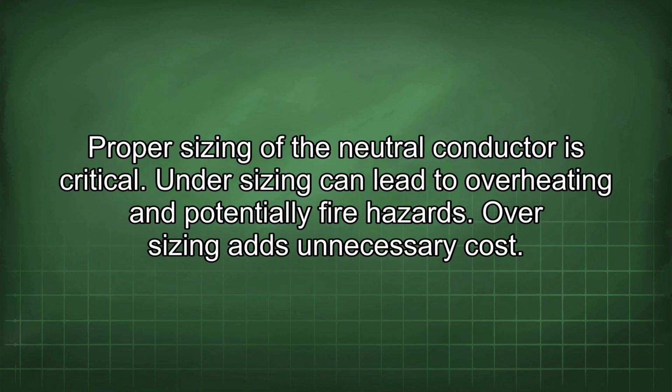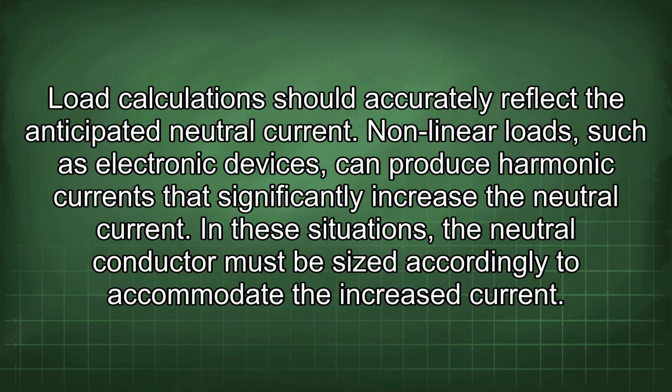Proper sizing of the neutral conductor is critical. Undersizing can lead to overheating and potentially fire hazards. Oversizing adds unnecessary cost. Load calculations should accurately reflect the anticipated neutral current. Nonlinear loads, such as electronic devices, can produce harmonic currents that significantly increase the neutral current. In these situations, the neutral conductor must be sized accordingly to accommodate the increased current.